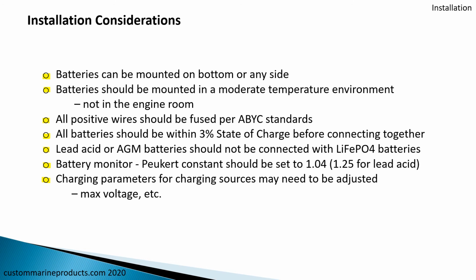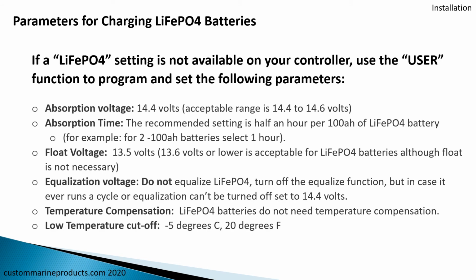So let's take a look at what these parameters might be. While you can use most lead acid chargers, to get optimum performance, here are the parameters that you'll want to program. The absorption voltage for these batteries is typically 14.4. You could go up to 14.6, but these batteries like a 14.4 absorption voltage. Lead acid is less than that, but some AGMs are close to that. The absorption time is recommended at a half hour per 100 amp hours of the battery. So if I have 200 amp hour batteries, I'd set the absorption length of time to 1 hour.